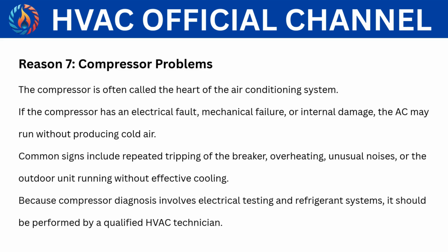Reason 7. Compressor problems. The compressor is often called the heart of the air conditioning system. If the compressor has an electrical fault, mechanical failure, or internal damage, the AC may run without producing cold air. Common signs include repeated tripping of the breaker, overheating, unusual noises, or the outdoor unit running without effective cooling. Because compressor diagnosis involves electrical testing and refrigerant systems, it should be performed by a qualified HVAC technician.